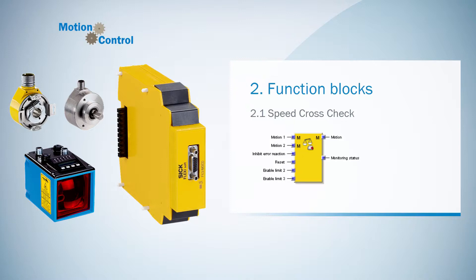Let me also give you a short overview of the different inputs and outputs of this function block. First we have the inputs Motion1 and Motion2 — here the signals of the encoders are connected, so the SpeedCrossCheck gets all the information provided by the encoders. Furthermore, there is the optional input InhibitErrorReaction, which can be used to prevent the error reaction in specific operational situations and reset the fault automatically.